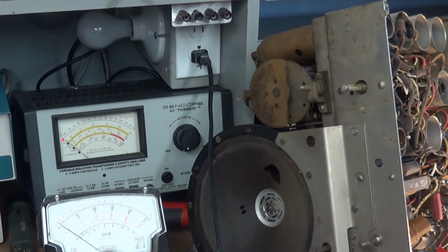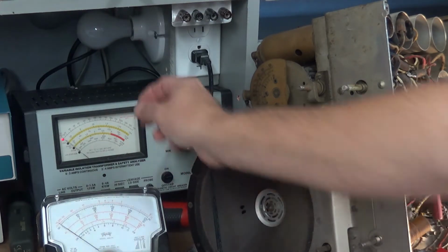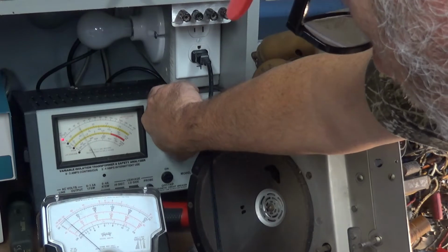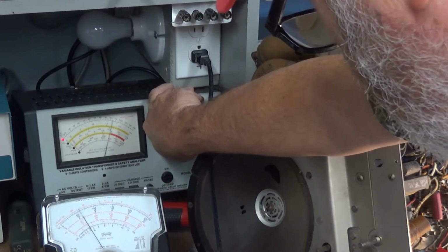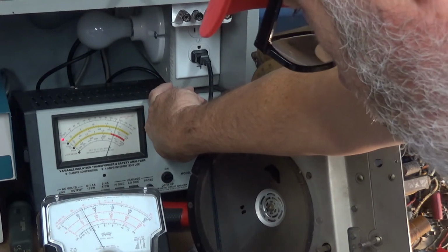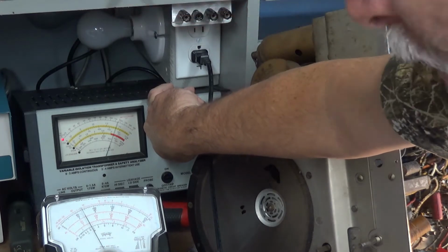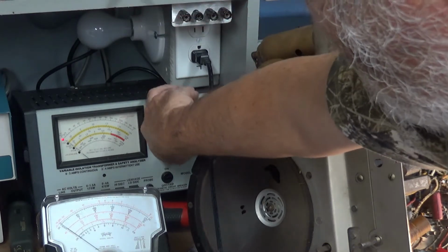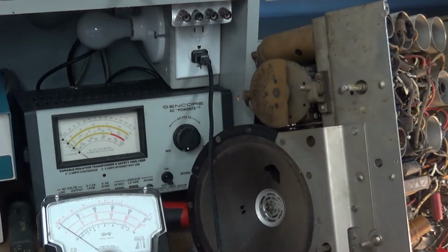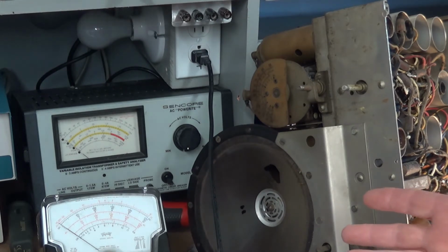The dial light says 2.6, and from my old memory we're getting about 2.8, so I suppose that's good. Great, so we've got the high voltage secondary good, our resistance checked good on that, we got proper high voltage out, and our tube filaments are right.